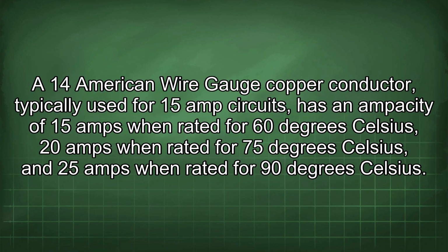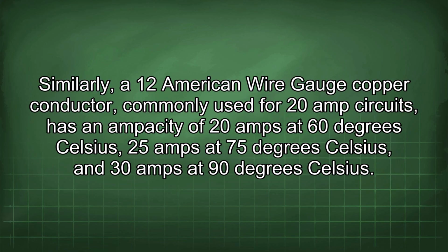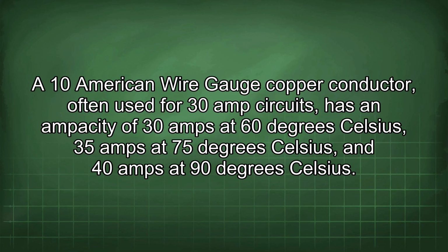A 14 American wire gauge copper conductor, typically used for 15 amp circuits, has an ampacity of 15 amps when rated for 60 degrees Celsius, 20 amps when rated for 75 degrees Celsius, and 25 amps when rated for 90 degrees Celsius. Similarly, a 12 American wire gauge copper conductor, commonly used for 20 amp circuits, has an ampacity of 20 amps at 60 degrees Celsius, 25 amps at 75 degrees Celsius, and 30 amps at 90 degrees Celsius. A 10 American wire gauge copper conductor, often used for 30 amp circuits, has an ampacity of 30 amps at 60 degrees Celsius, 35 amps at 75 degrees Celsius, and 40 amps at 90 degrees Celsius.